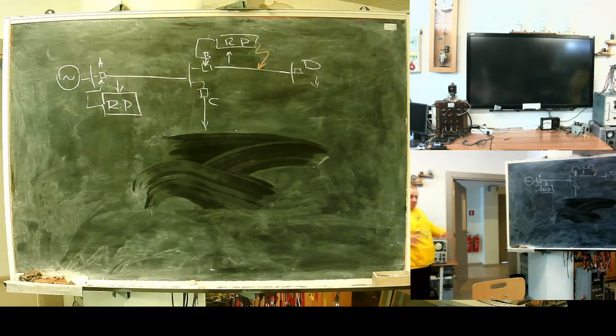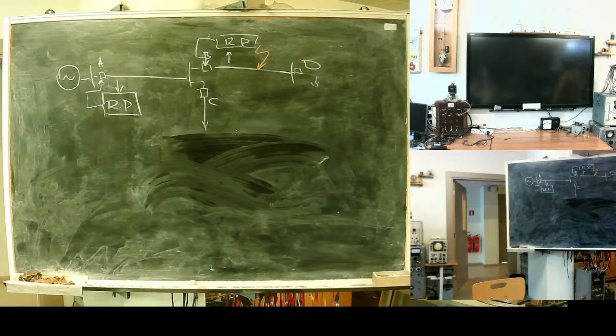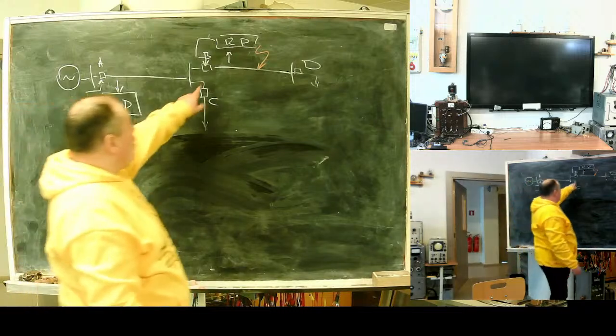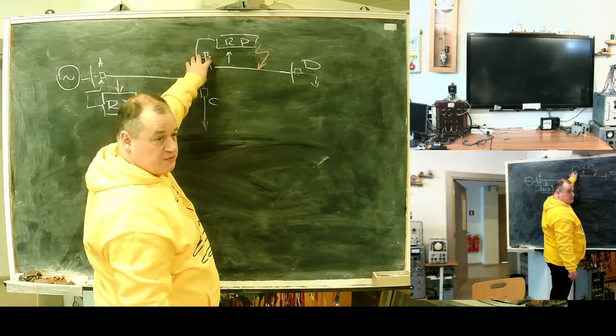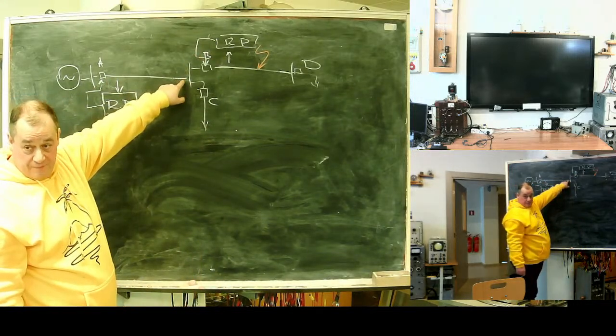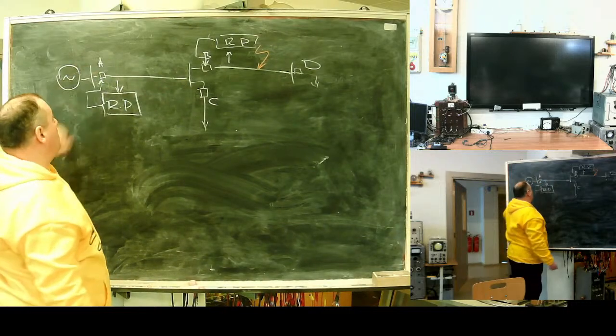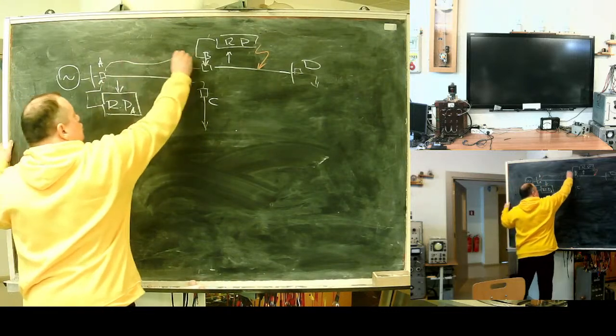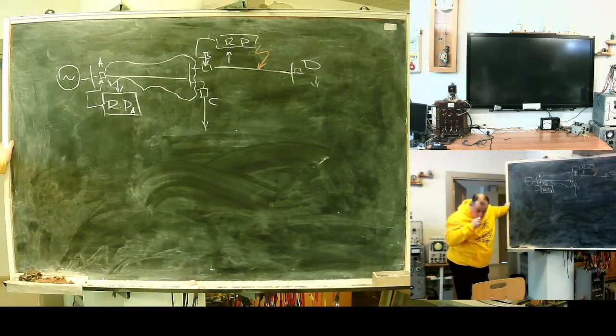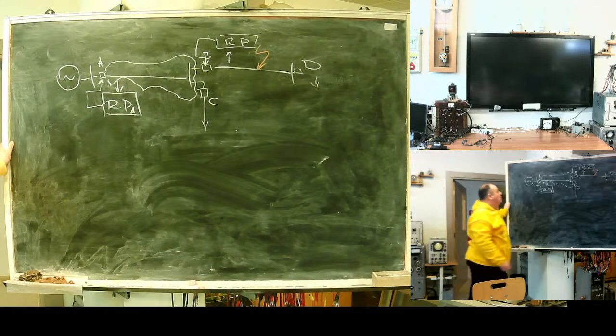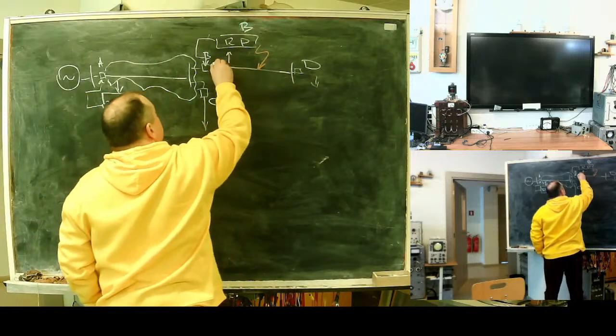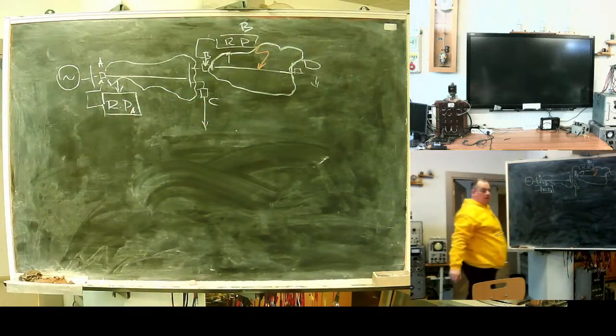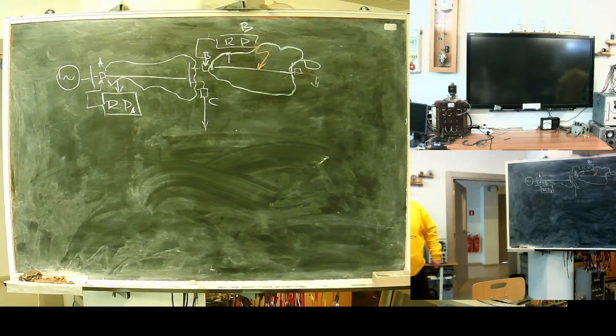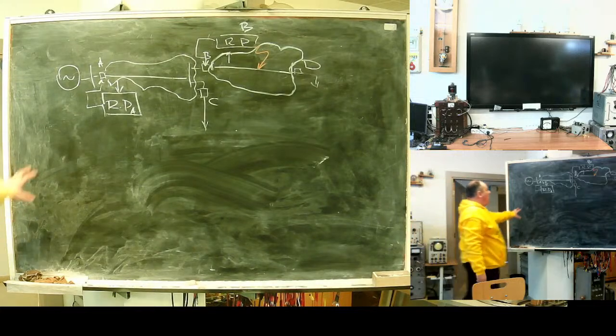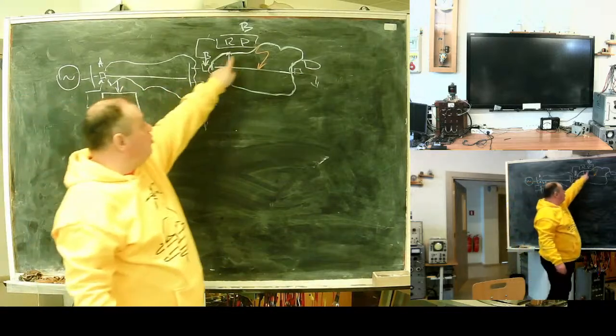For this device, for its brain, for its logic, I can specify a very important thing: the protected zone. All faults on this line should be cleared by switch B. All faults in line A, in the first line, should be cleared by A. So this device with A should take a close watch on everything inside the white balloon. Device 2, this one, B, should also keep a close watch, and if damaged, the line is disconnected. This is the protected zone for A, white. Blue is the protected zone for B.